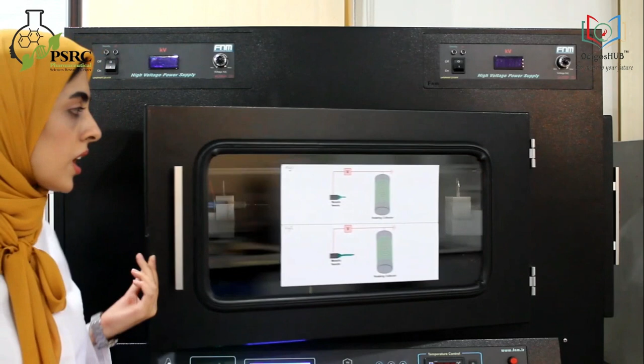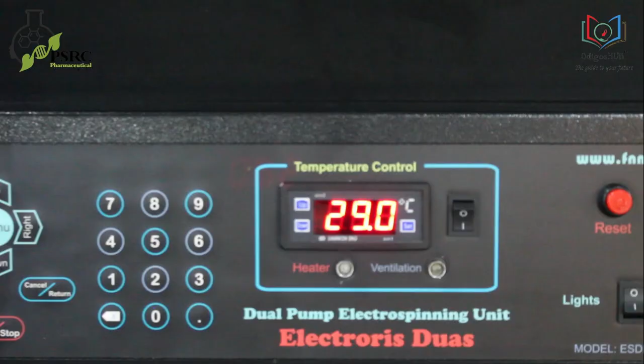Active session. According to which pumps you are using, you can choose both left or right. Another important part of the panel is temperature control. We turn it on by pressing the switch. You can change the temperature after pressing the set key and up and down. Our device temperature range is from 25 to 45 degrees centigrade. If you turn on the temperature control, ventilating happens with these two fans. They start ventilating every 150 seconds for 60 seconds.